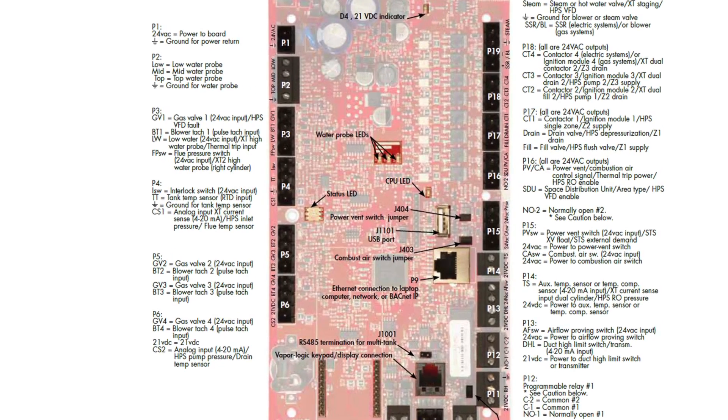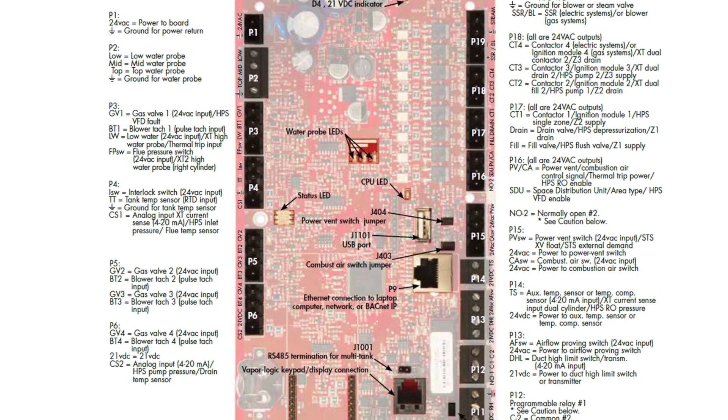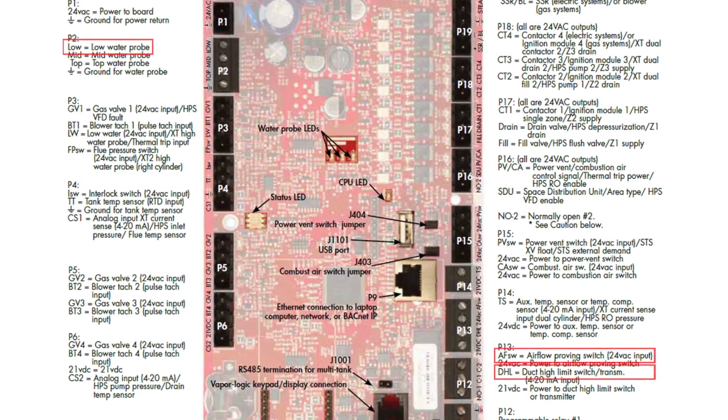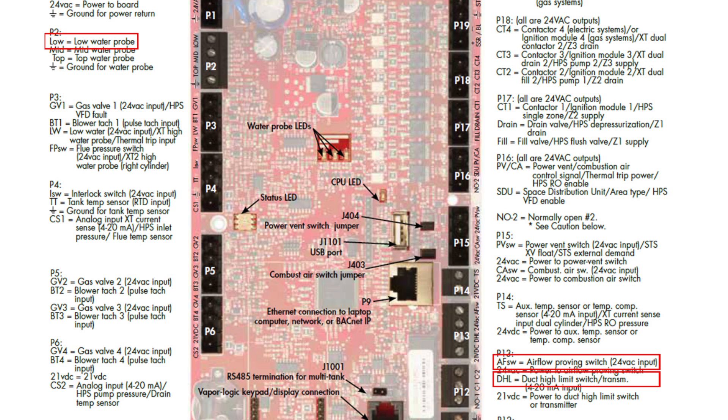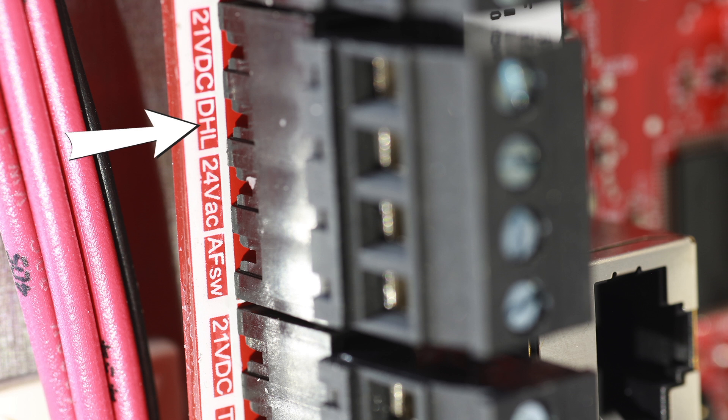All safety devices in the control circuit should be cycled on and off to verify they are functioning. These include high limit device, airflow proving switch, low water level probe, or float switch.